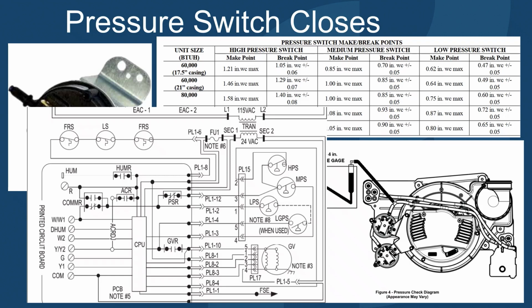Also, don't overlook the fact that you should check the wiring of the pressure switch circuit where it enters the board to eliminate any break in the wires that go out through the furnace to the pressure switches.